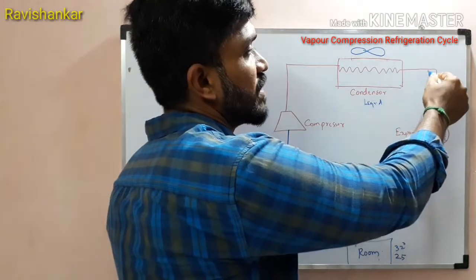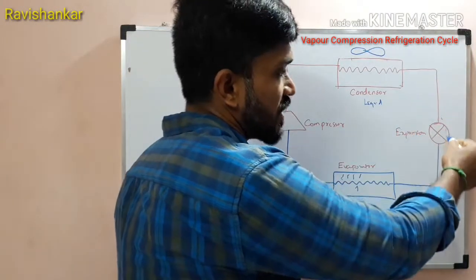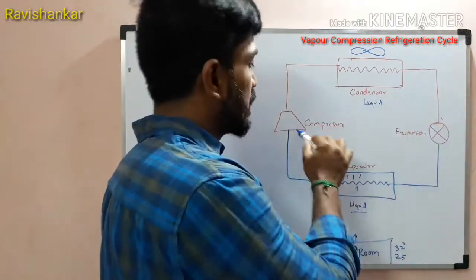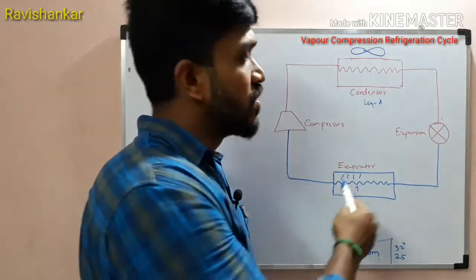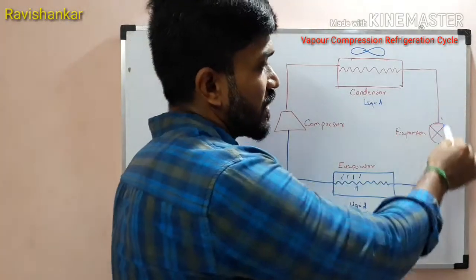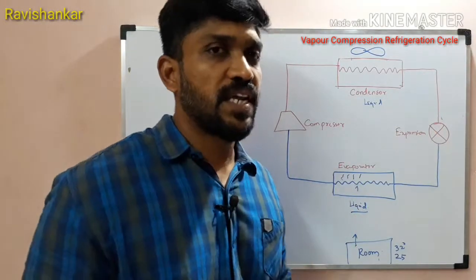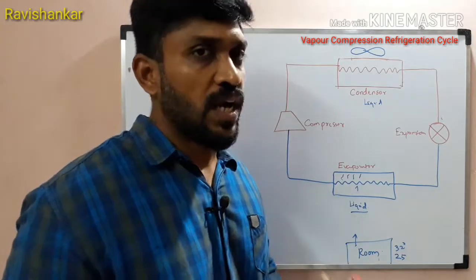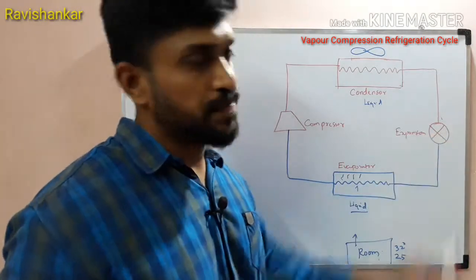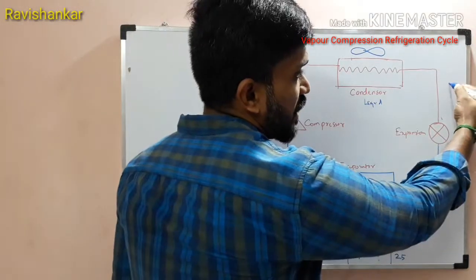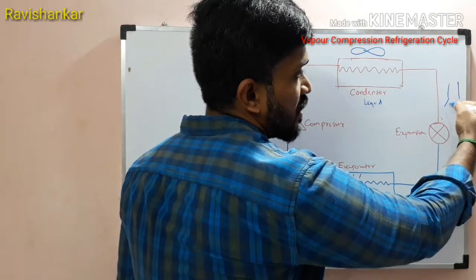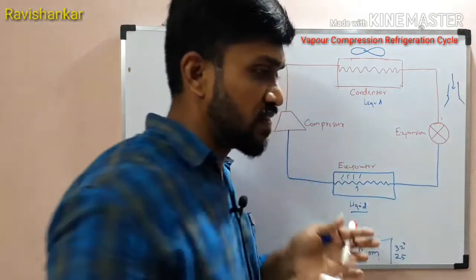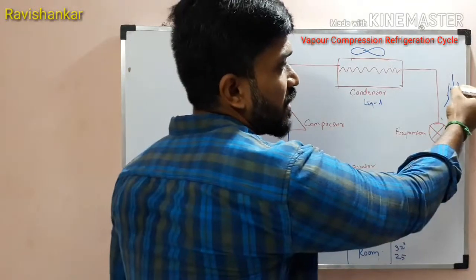Now we will put the liquid into the expansion device. In this expansion device, I will continue to cycle this. In the expansion device, there is high-pressure liquid — the high-pressure liquid becomes low-pressure. That's why we are using this expansion device. There is a restriction in this pipe — you can see the pressure drop all the way down.